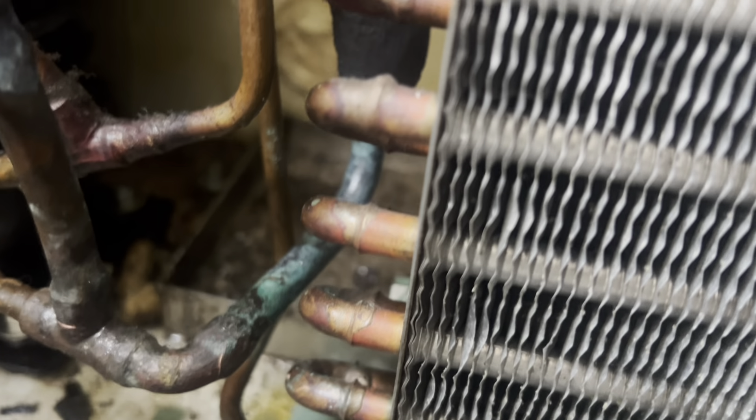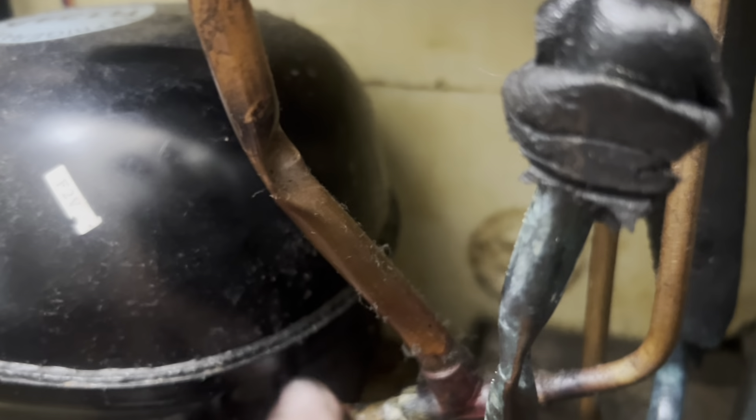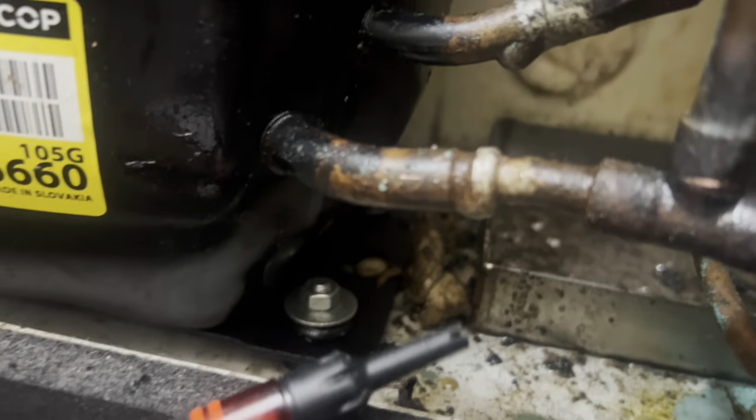Once they do that, we're going to have air moving in places that'll make things more difficult for me. This is definitely oil-laden right here, for sure. But we may just be so low that we're not bleeding much. Hopefully I don't see the rust I thought I would — hopefully we've just got some very repairable leak. This is not one that uses the condensate loop, so it's not leaking from there.